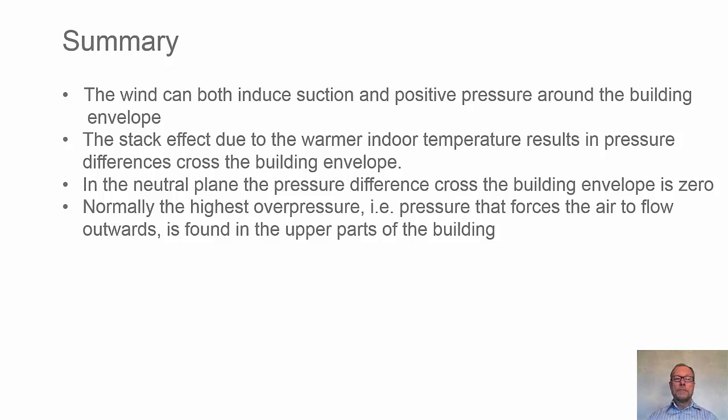Summary. The wind can both induce suction and positive pressure around the building envelope. The stack effect due to the warmer indoor air results in pressure differences across the building envelope. In the neutral plane the pressure difference across the building envelope is zero.